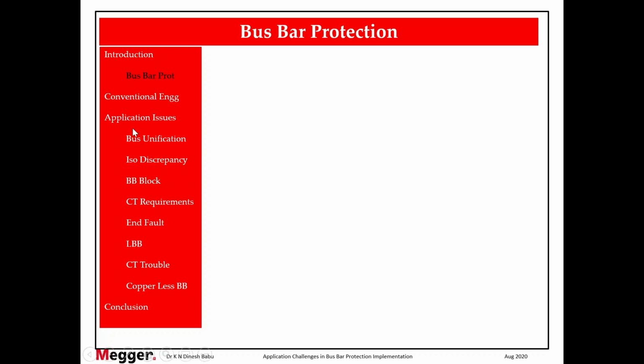We are going to focus more on these areas: the bus unification concept, isolator discrepancy, blocking logics, how the busbar should be blocked, the requirements of the CT, how many CTs, where should it be located, what is end fault, what kind of tripping should we give. So should we trip the busbar or should we trip the remote end?